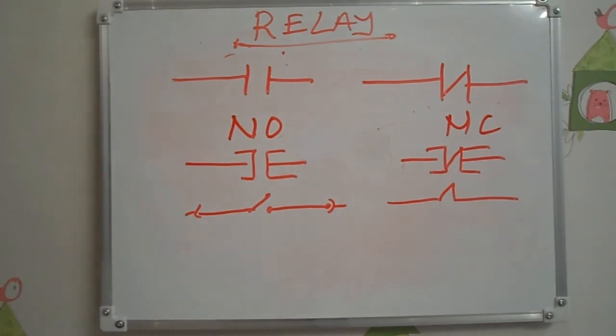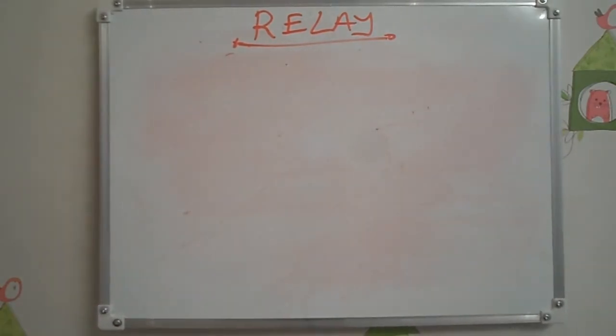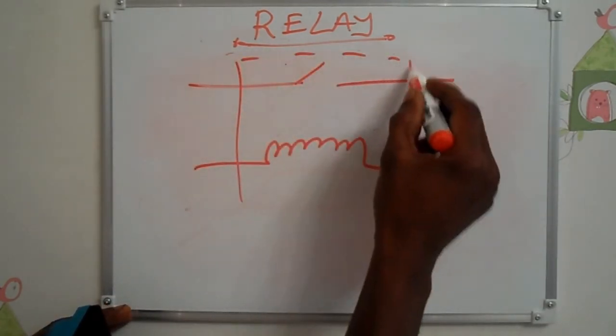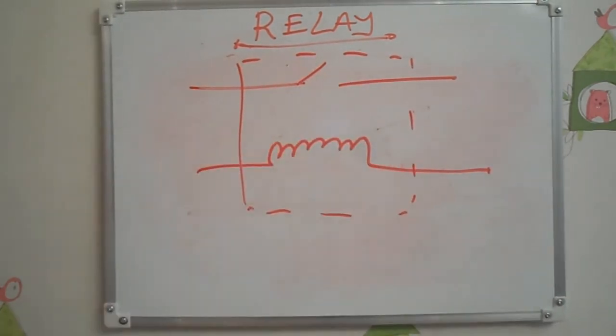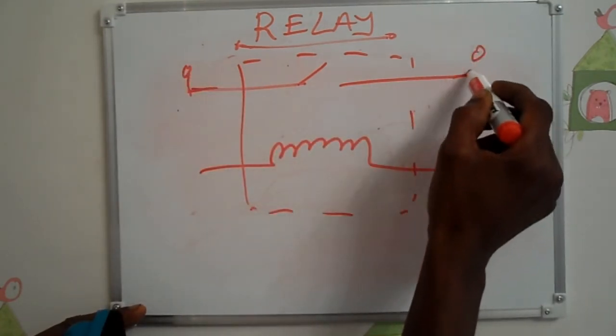When you know about relay, you will see how it is going to make your design perfect. The relay is divided into two parts: the coil part and the contact part. The symbol shows the contact up here, and this is the coil down here. We have four pins: pin 1, 2, 3, and 4. This coil can be 24 volts DC, and this contact can be 10 amps AC — meaning you can power this relay with DC voltage while AC current passes through the contact.